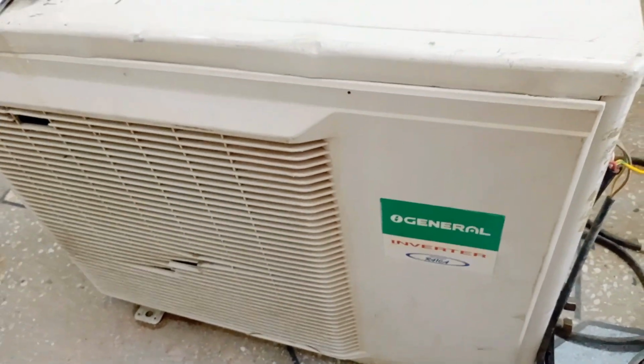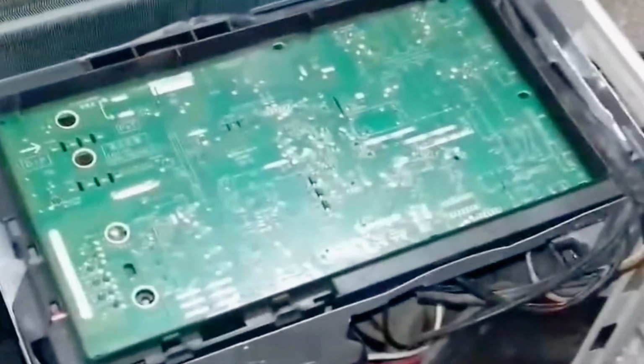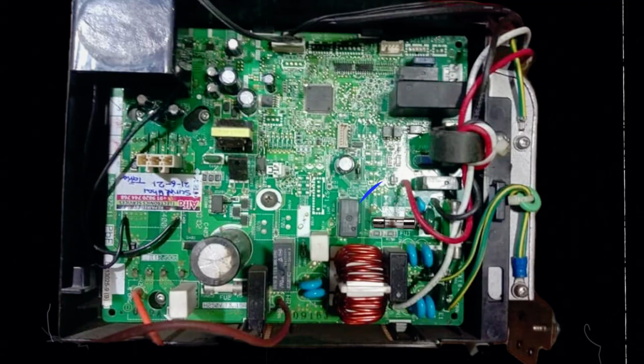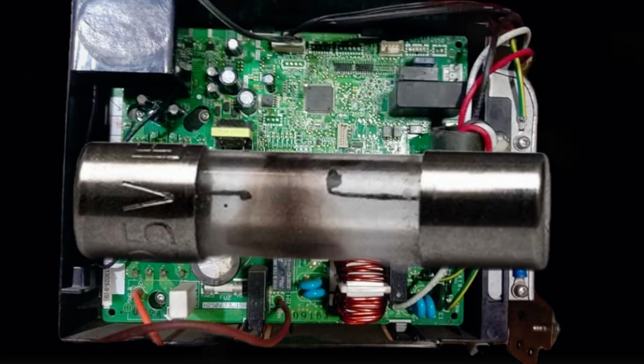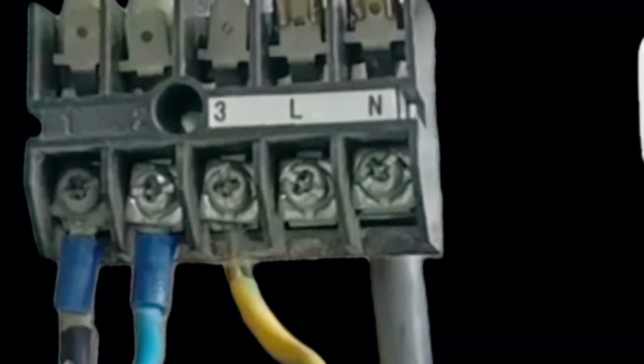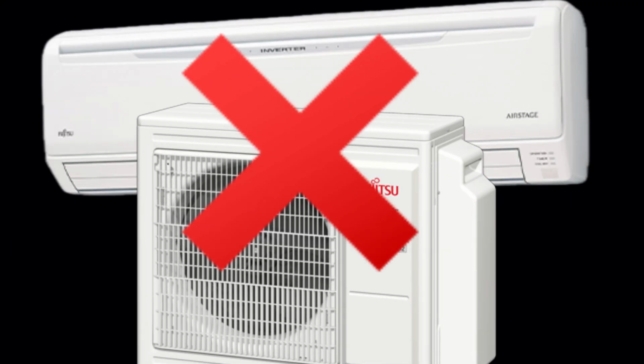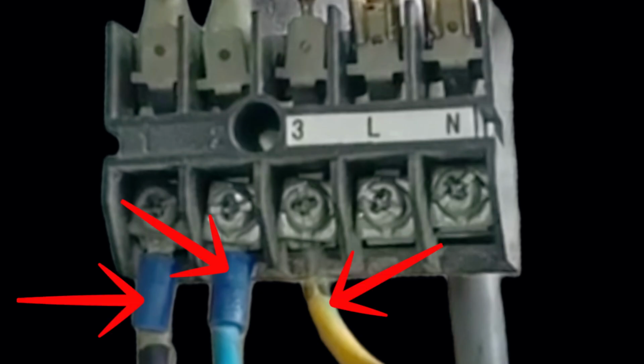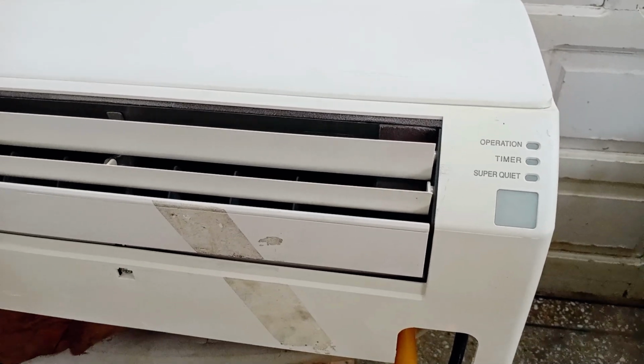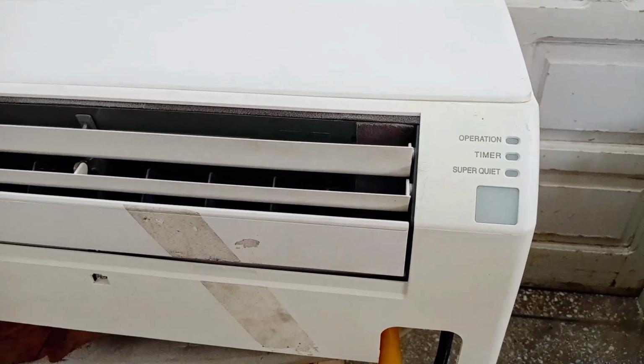The fault might lie in the outdoor circuit board. Either the circuit board is not functioning at all, the fuse on the circuit board has blown, or the communication wire between the indoor and outdoor units has disconnected. All the wires could also disconnect due to any reason, or the connections while installation might have reversed. Whenever any of these problems occur, the air conditioner will display two blinks.